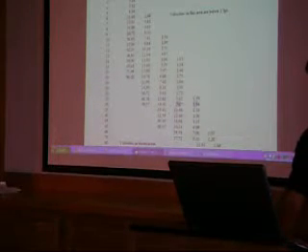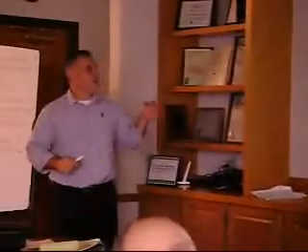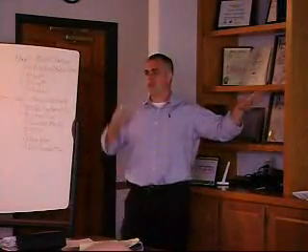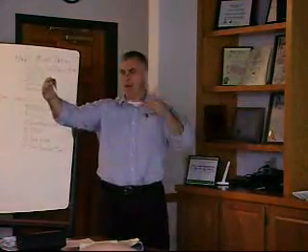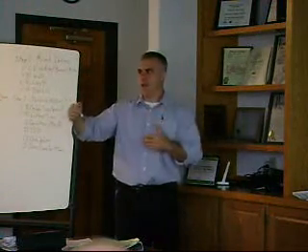2-inch pipe: 1.94, about 2 feet of friction loss per 100 feet of pipe. If I've got 200 feet of 2-inch pipe to pump through, I've got 4 feet of friction loss versus 16 foot for 1.5 inch. So when you're choosing pipe diameters on your force main, which is our next step, and manifold, normally the manifold matches the force main. Normally they're the same. Those are the reasons. You're looking ahead and saying, my pump is going to be big if I'm not careful.